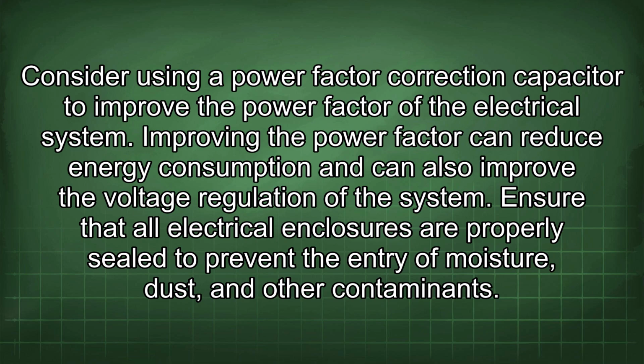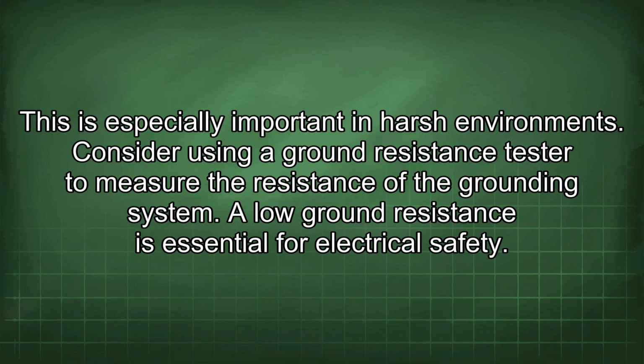Consider using a power factor correction capacitor to improve the power factor of the electrical system. Improving the power factor can reduce energy consumption and can also improve the voltage regulation of the system. Ensure that all electrical enclosures are properly sealed to prevent the entry of moisture, dust, and other contaminants. This is especially important in harsh environments.